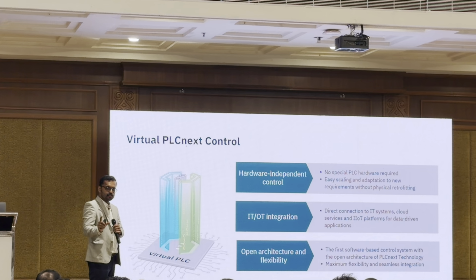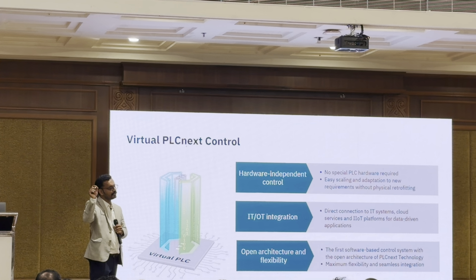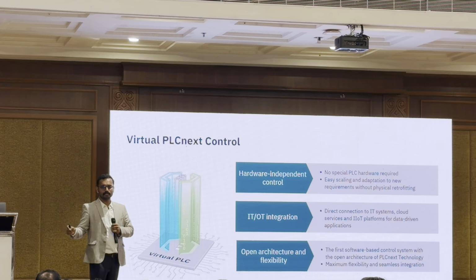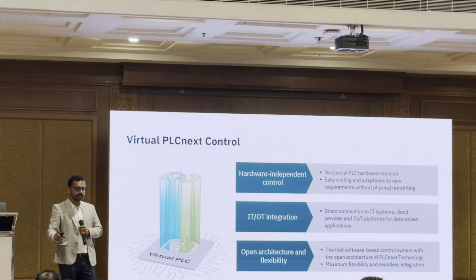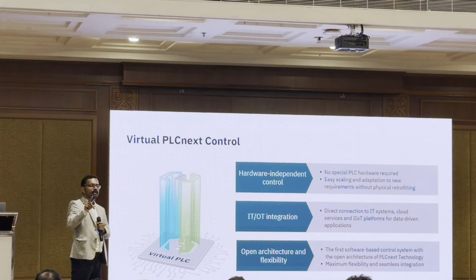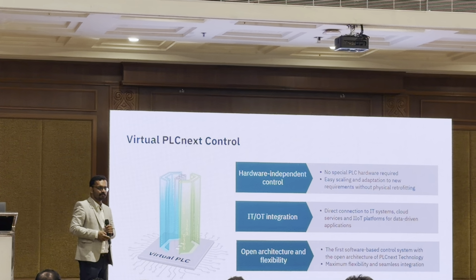But the advantage of virtual PLCs comes with 1000 IO points, 1000 variables, 5000, 10,000, 50,000, 100,000 variables or IO points. You need not change your PLC license hardware. Keep the set capacities and run these virtual PLCs with multiple instances inside a PC kind of hardware. That is the concept of virtual PLCs.